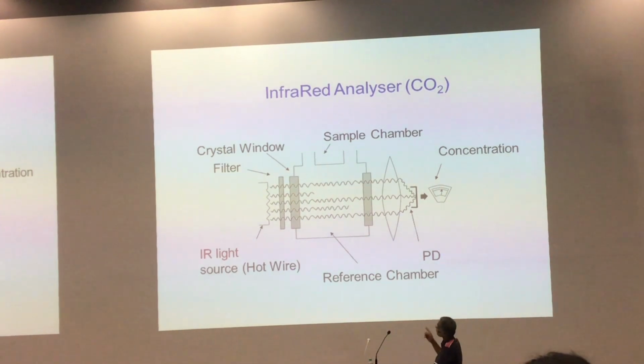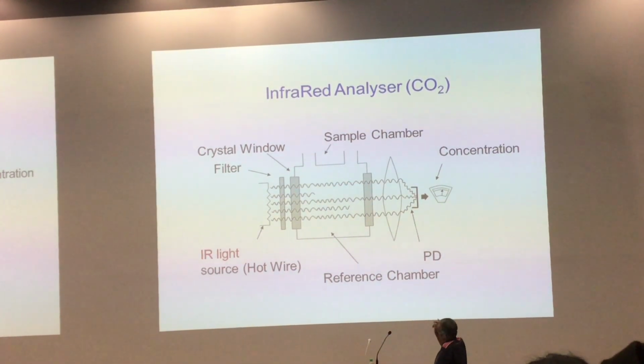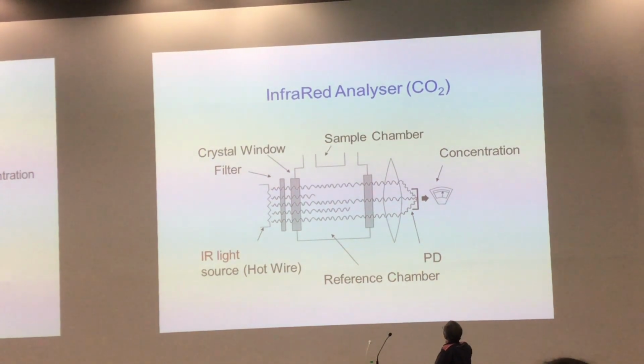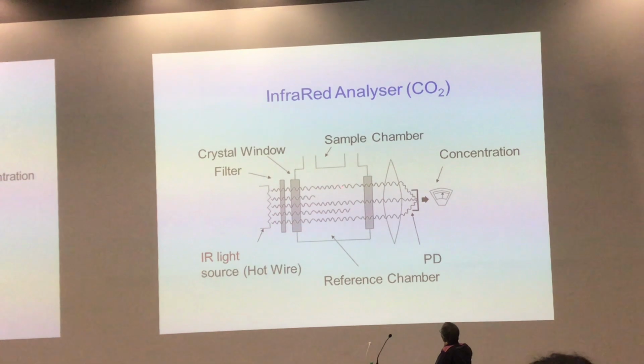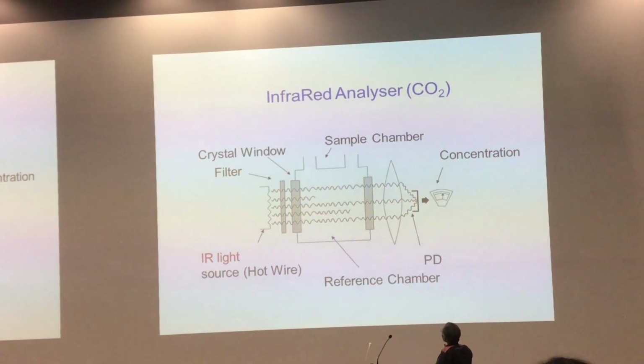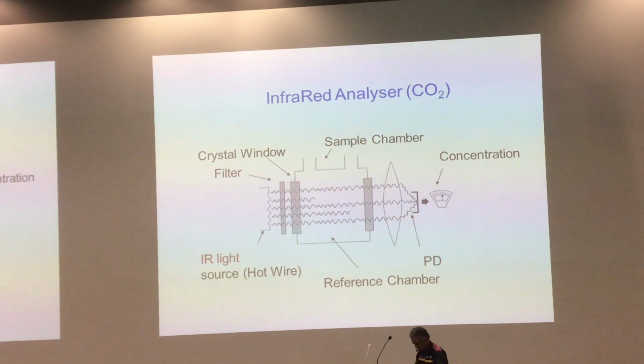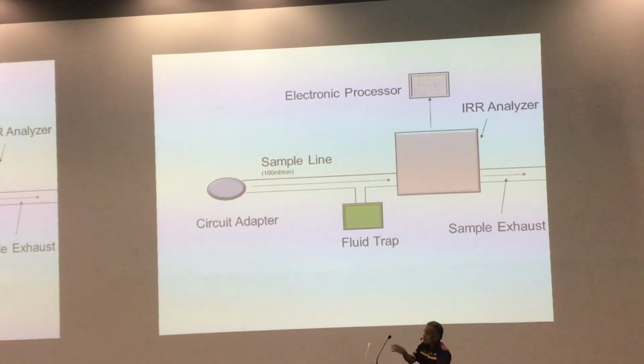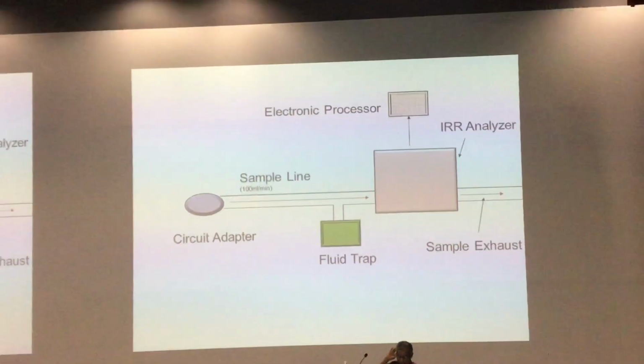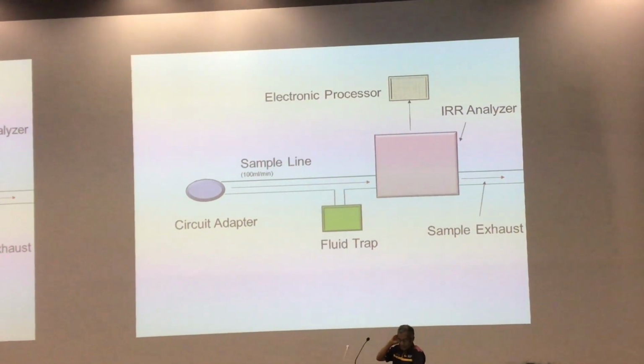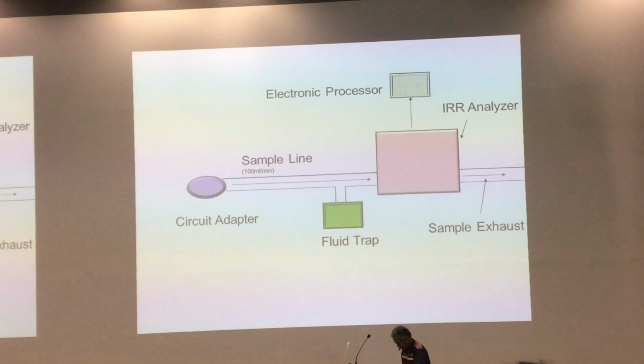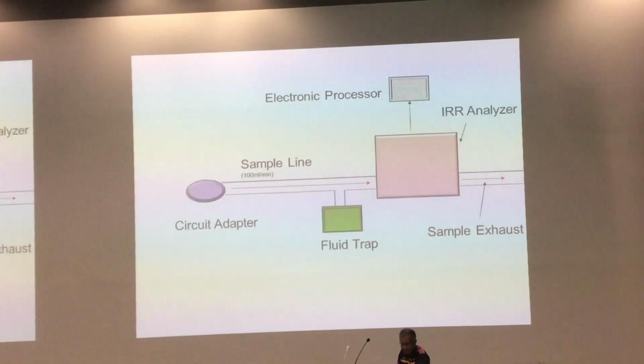They get the ratio between the sample chamber and the reference chamber. Then the amount of CO2 is calculated simply because CO2 here will absorb infrared, and we measure the intensity of infrared. Then we compare with the reference. So this is the principle. You have to know the principle only. Now, the one we are using in the OT is the side sampling system, side stream.